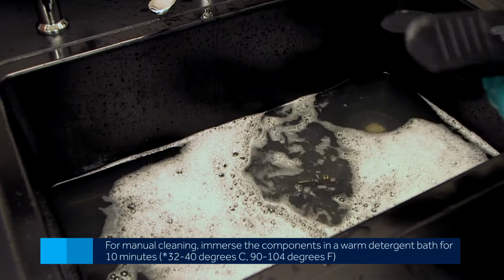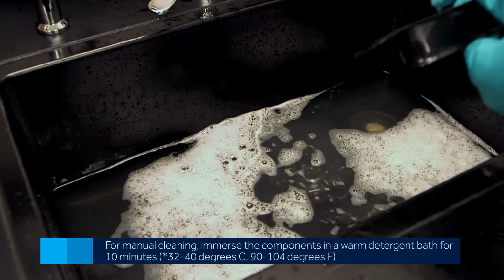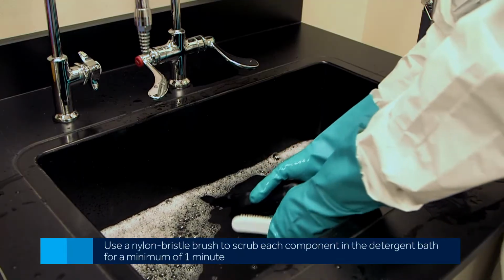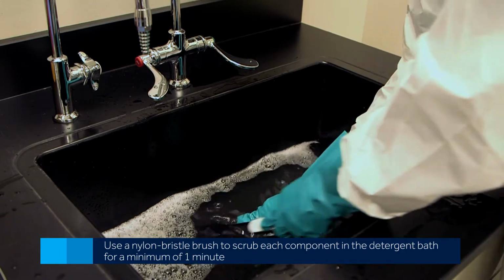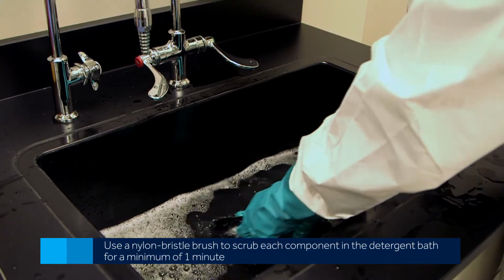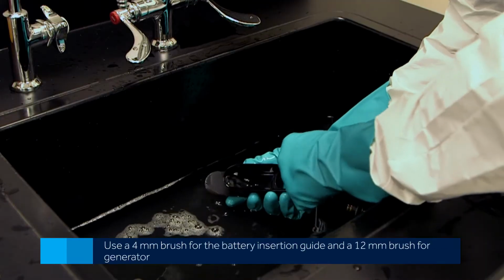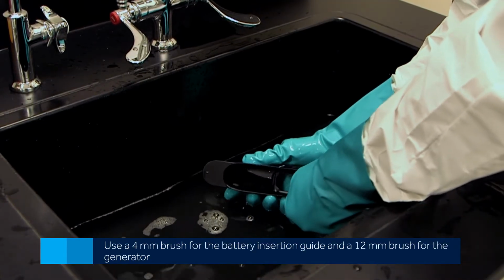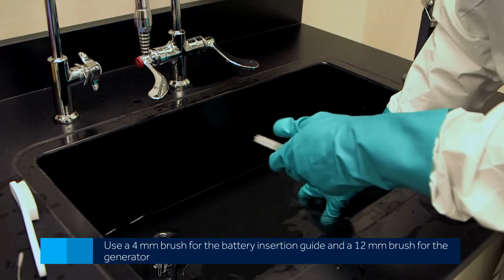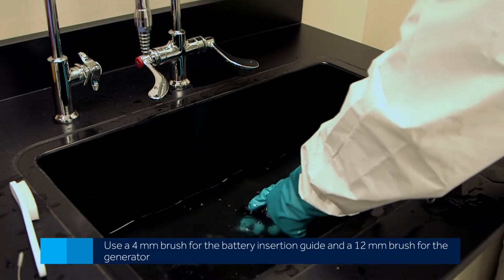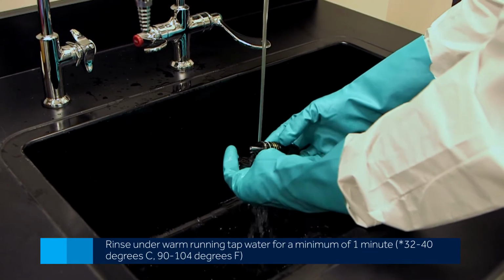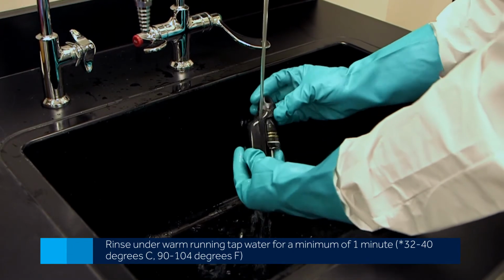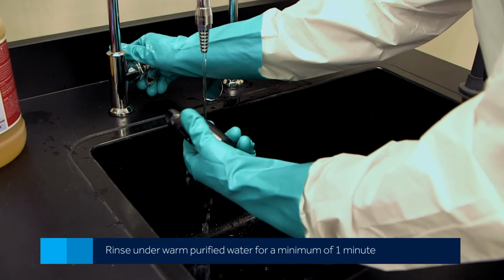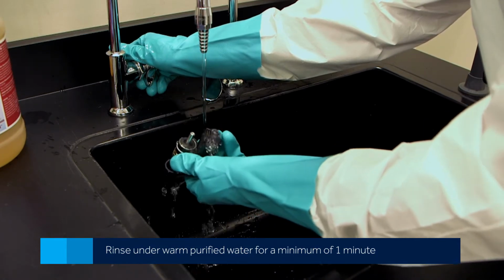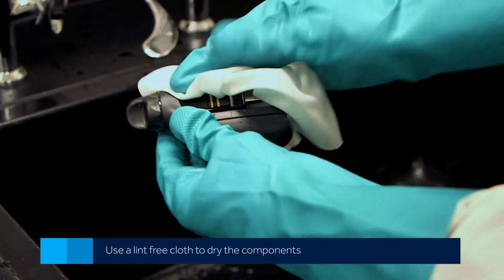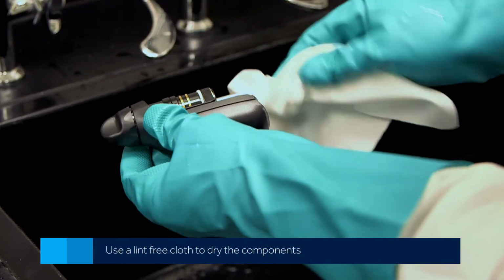For manual cleaning, immerse the battery insertion guides and generator in a warm detergent bath for 10 minutes. Use a small, soft, nylon bristled general instrument cleaning brush to scrub each component in the detergent bath for a minimum of 1 minute. For hard-to-reach crevices, use a 4 mm soft nylon bristle brush for the battery insertion guide, and use a 12 mm soft nylon bristle brush for the generator. Rinse each component under warm running tap water for a minimum of 1 minute. Perform a final rinse under warm purified water for a minimum of 1 minute for each component. Use a clean, soft, lint-free cloth to dry the components.